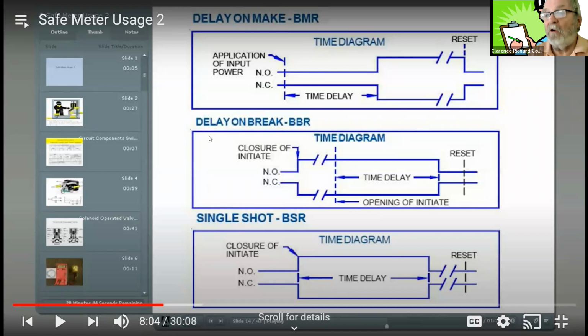And then maybe you're going to want a delay on break. That means if something happens, it's going to initiate and close its contacts right away, and after a certain amount of time goes by, it's going to take it away. That's a delay on break. Then you can have a single shot, where when something happens, it's just going to energize for a certain amount of time and then de-energize.